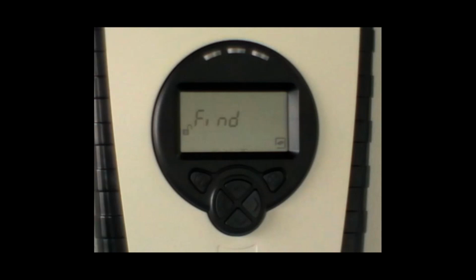This interrogates the system to see how many detector heads are connected. The display will count down from 60. After 60 seconds, the number of detector heads found will be displayed, 1D or 2D. Press tick to accept if the number is correct. We are now going to align each detector head in turn.